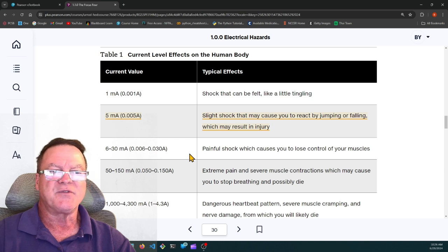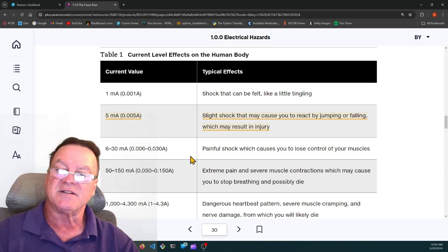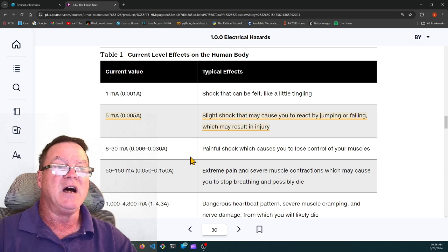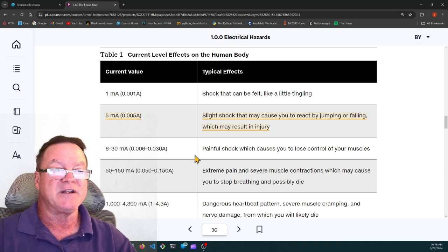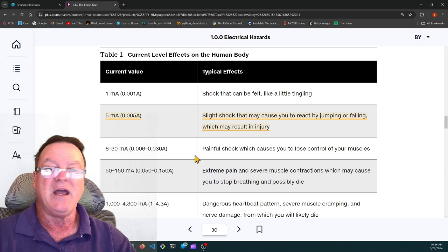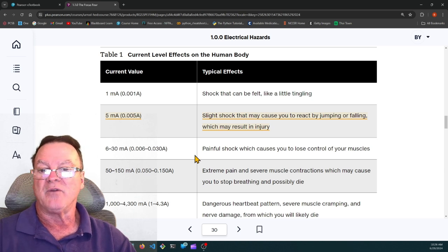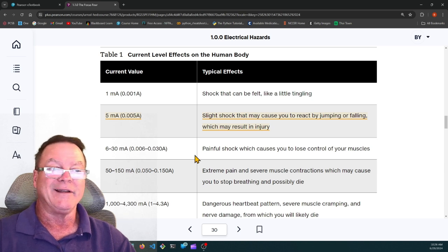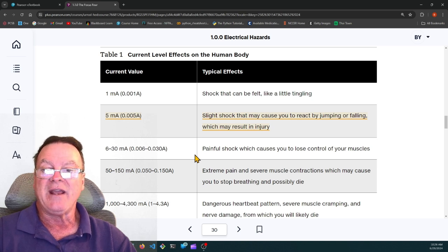Some say as little as 300 milliamps will kill you. Some say as little as 75 milliamps will kill you. I saw one reference material that said as little as 50 milliamps can kill you. And there was one reference material that said if you are above the let-go threshold and you get hung up on electricity, you could die in as little as 20 milliamps. If you cannot get off the line, if you're stuck and you can't let go, if it's above your let-go threshold, you could die.